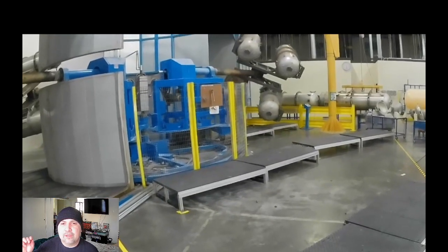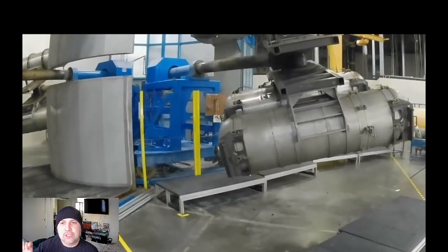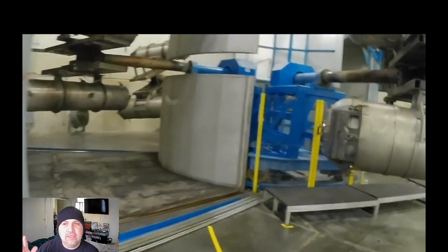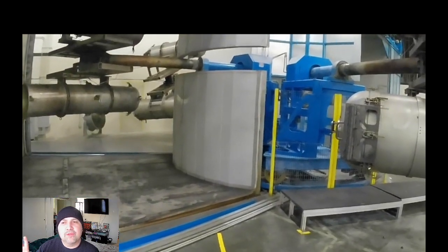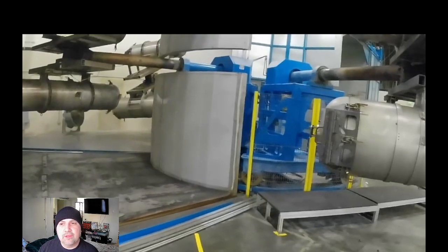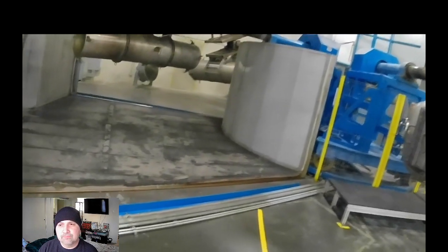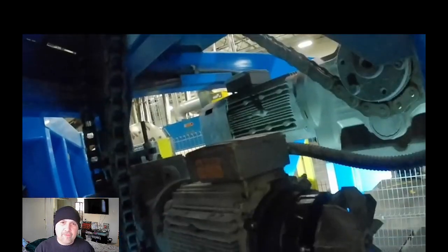So there's actually three arms operating on this molding machine, and it's this last arm that is the issue. It has a rotate, and then it has a plate motor that kind of twists the molds in another direction. And that plate motor was not operating. Okay, we are right there. Ooh, that's not good. That is not good. So I'm trying to operate the motor, and it's not doing anything. So I had to decide if it was a mechanical failure or if it was an electrical failure.